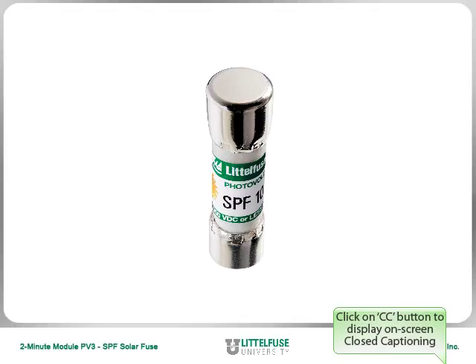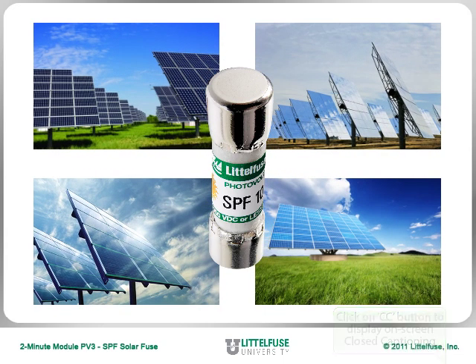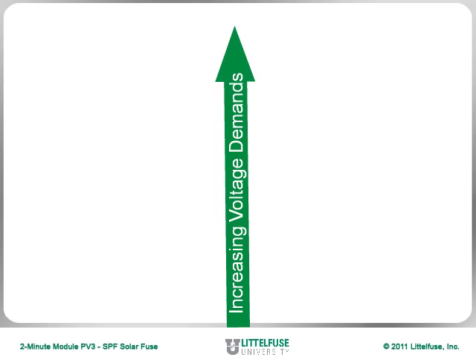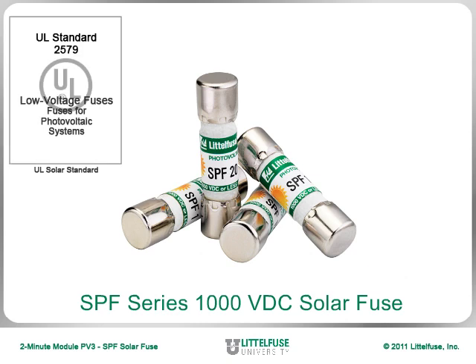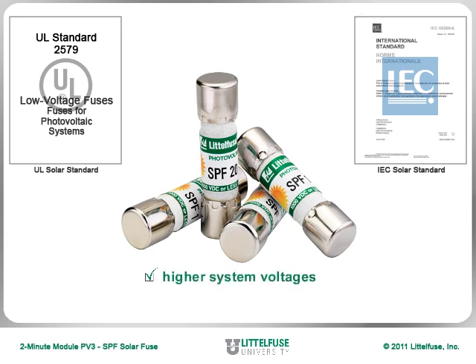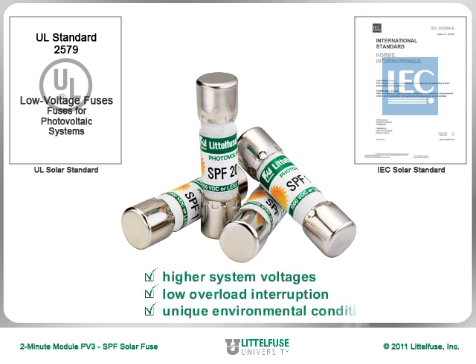The 1,000 volts DC rated SPF series of solar fuses have protected thousands of strings in photovoltaic or PV systems. As voltage needs have increased, so have the corresponding standards. The SPF series now meets both UL2579 and IEC60269-6 requirements for higher system voltages, low overload interruption, and unique environmental conditions.